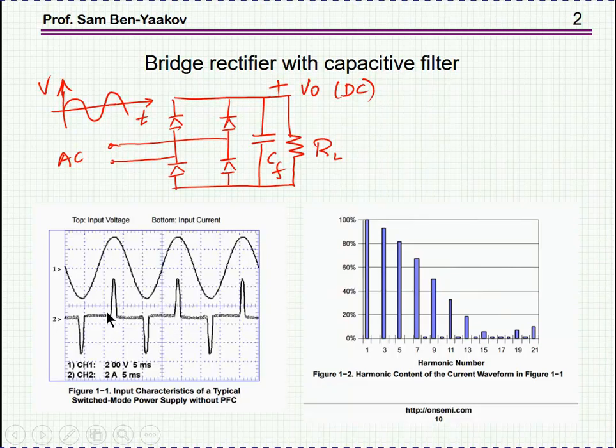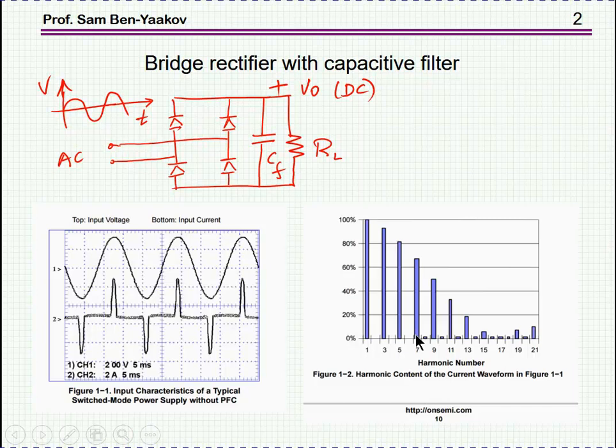Therefore, there's a lot of distortion here, and this is the harmonic composition of this current. As we can see, there are many components of higher frequencies than the main frequency of the line. This is now forbidden in most countries around the world, and in fact, equipment must be designed such that the current will be almost sinusoidal.